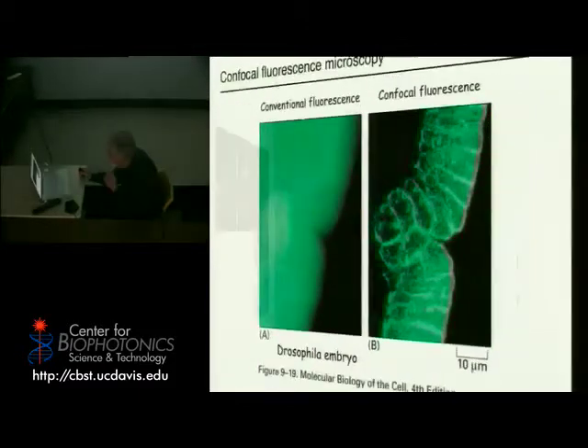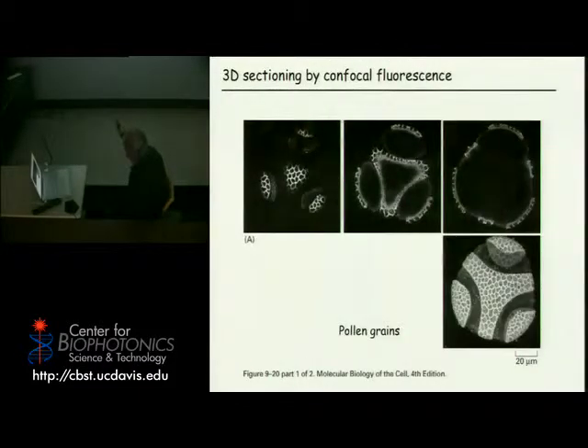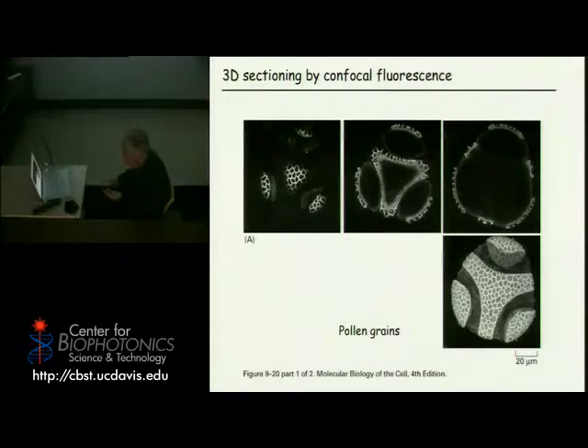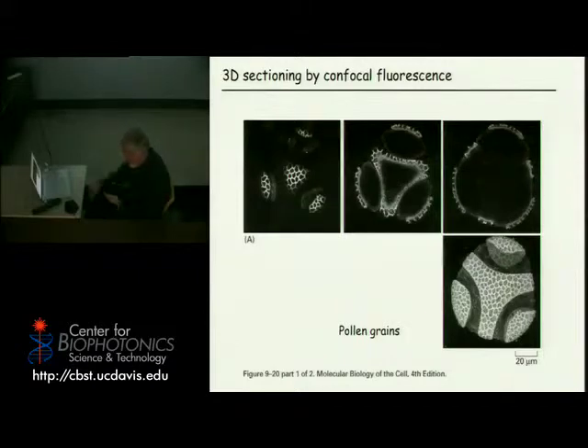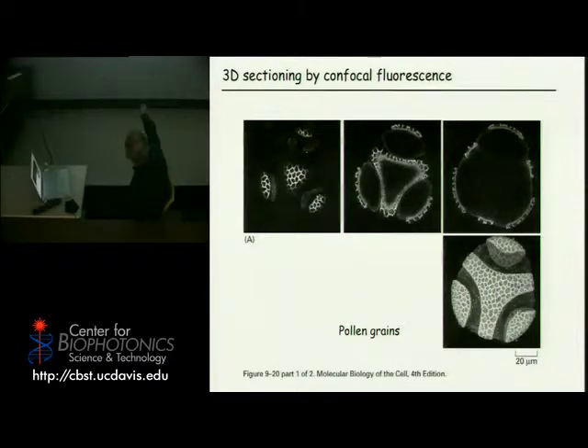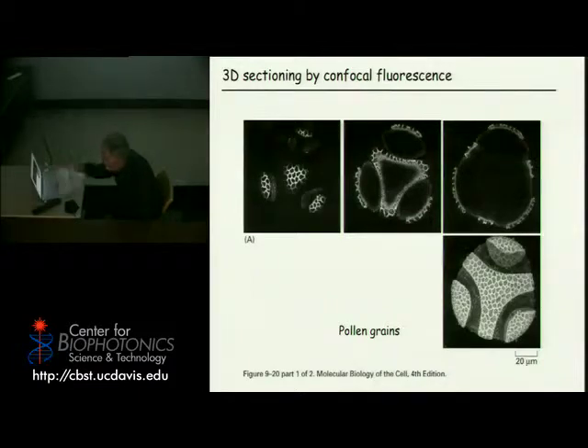This gives you a comparison of a confocal microscope and a conventional microscope looking at a fluorescent-stained Drosophila embryo — you can see the improvement. It's a scheme where you're not looking at the entire image at once: you look at one point at a time, scan that point back and forth over the sample, and use a computer to reconstruct what the sample looked like. This gives higher resolution and also a 3D effect called optical sectioning — you can move the focal plane up and down and scan through the object.